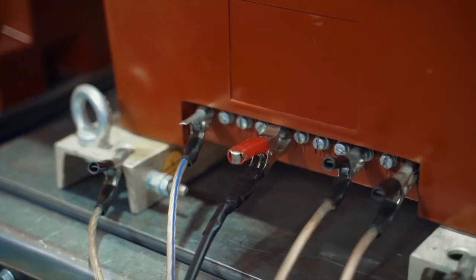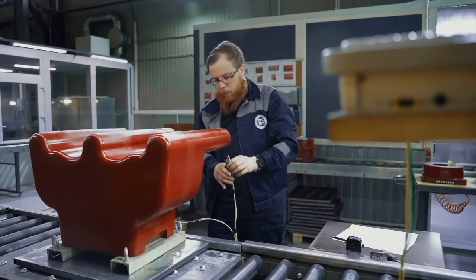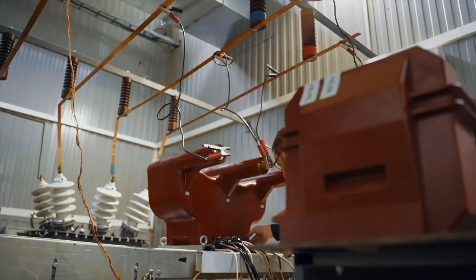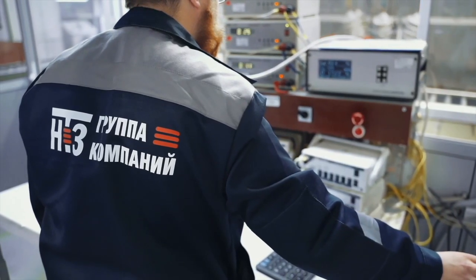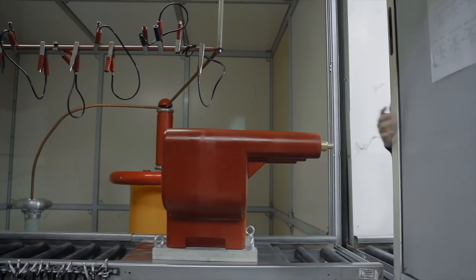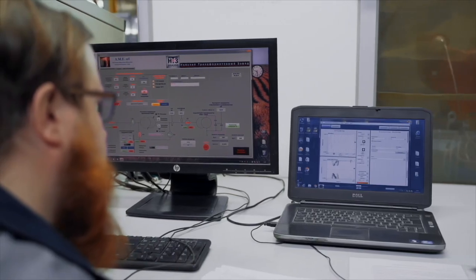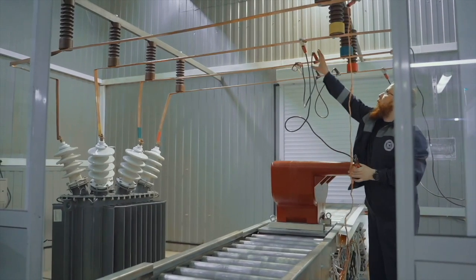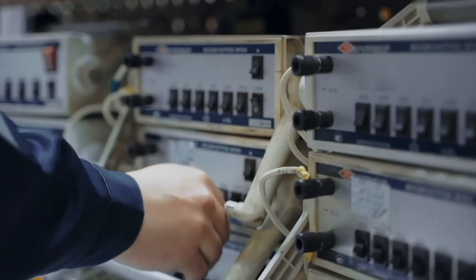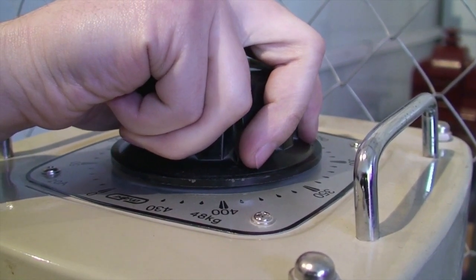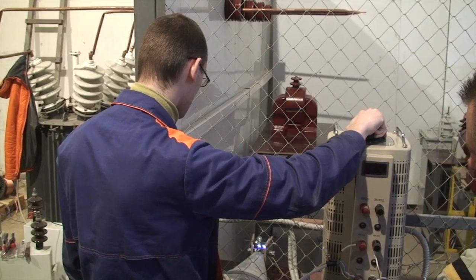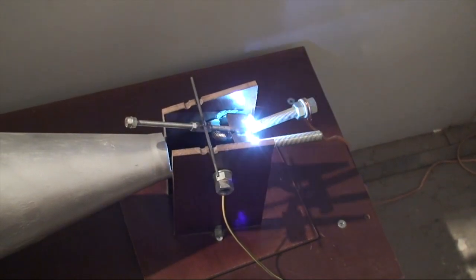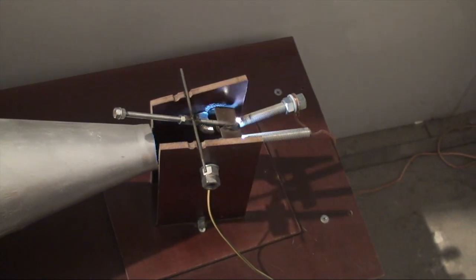To confirm the anti-resonance properties, a test procedure was developed at the NTZ Volkhov factory and a testing laboratory was built to test voltage transformers for resistance to ferroresonance effects in 6 to 35 kV networks. This laboratory allows simulating real emergency modes of voltage transformer operation, namely arc single-phase phase-to-earth faults, not-full-phase network operation modes, and spontaneous displacement of the neutral. Testing equipment allows checking the transformer during testing for the appearance of harmonic and subharmonic stable ferroresonances.